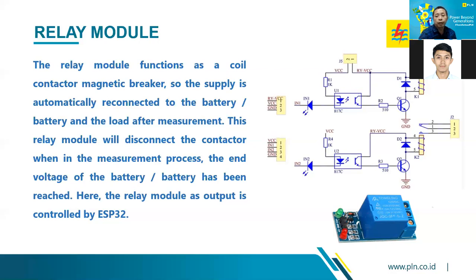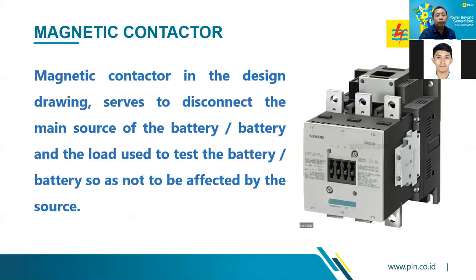Besides the electronic circuit, number two, magnetic contactor. The magnetic contactor in the design drawing serves to disconnect the main source of the battery and the load used to test the battery, so as not to be affected by the source.